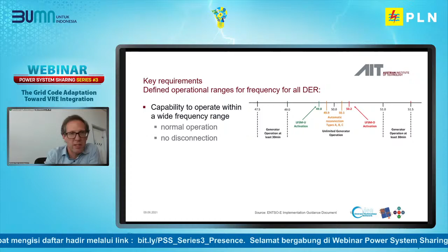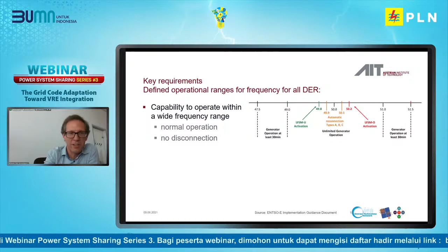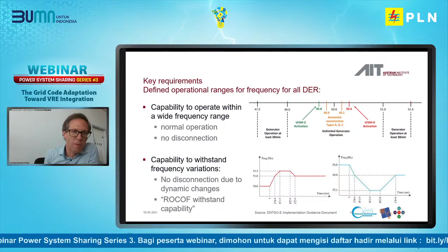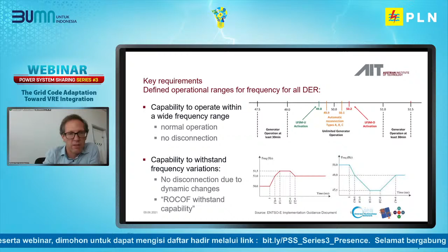Just to highlight some of the key requirements currently existing in Europe: we have already seen these defined frequency ranges, and I was very happy to see that they are now also included in the recent revision of the Indonesian grid code, or the Sumatra grid code. There is also a requirement to define the capability to withstand frequency variations. This means the generators are not allowed to disconnect due to transient changes of the frequency. The European grid code uses the terminology RoCoF withstand capability to define these requirements.